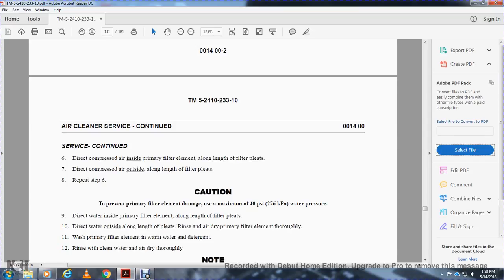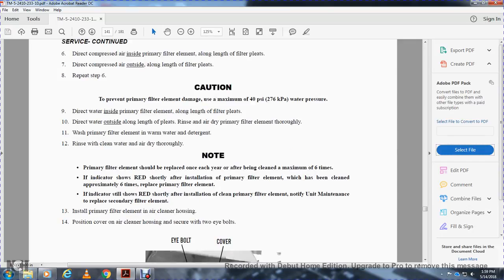Repeat step 6. Caution: to prevent primary filter element damage, use a maximum of 40 psi water pressure. Direct water inside primary filter element, along length of filter pleats. Direct water on the outside along the length of the pleats. Rinse and air dry the filter element thoroughly. Wash the primary filter element with water and detergent. Rinse with clean water and dry thoroughly. Note: the primary filter element should be replaced once each year, or after being cleaned a maximum of 6 times.